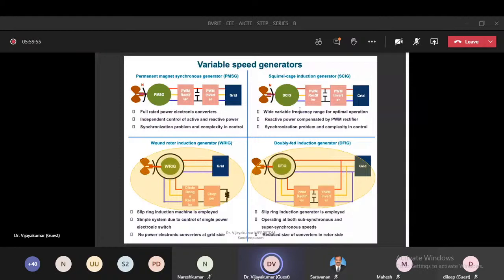When we come to the permanent magnet synchronous generator, we already have the permanent magnets in the field. So depending upon the wind velocity, you will get variable voltage and variable frequency at the stator terminals, right? Here also we use a back-to-back converter, so that variable voltage, variable frequency can be converted into variable voltage DC. Then that can be fed into the grid by using the grid tie inverter. The same way here, it will take the magnetizing current from this converter and it can give variable voltage and variable frequency depending upon the wind velocity.